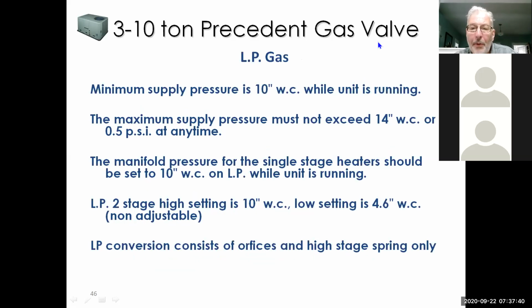All right, so on LP gas, a little different animal. There is a specific LP kit for each unit. Minimum pressure 10 inches. And again, maximum is 14. We don't want to exceed that 14 inches on LP. When you're working with single stage units, the gas pressure should be set at 10 inches on high fire for manifold pressure. On the two-stage units, we're looking for 10 inches on high and 4.6 on low.